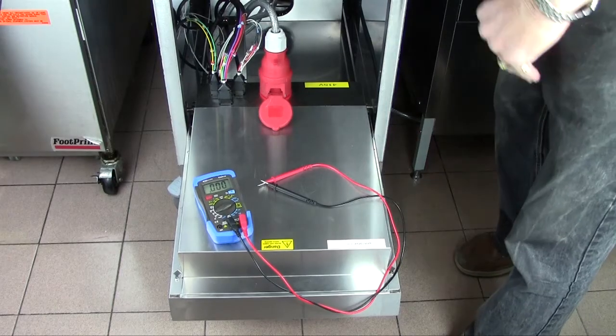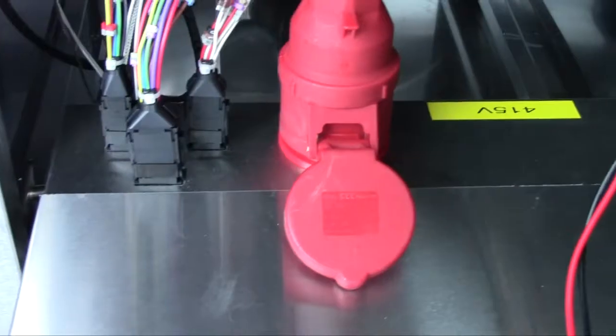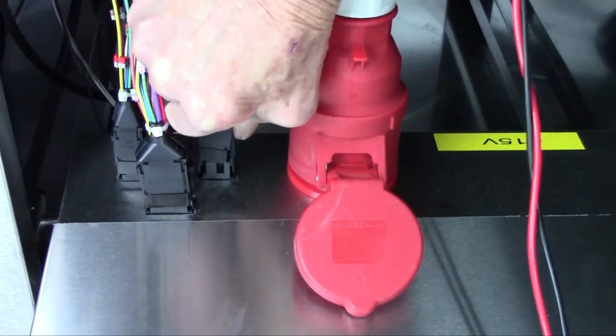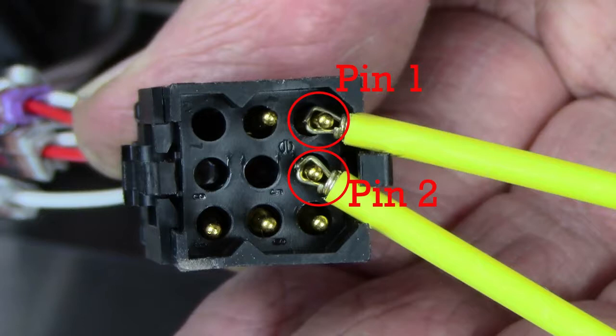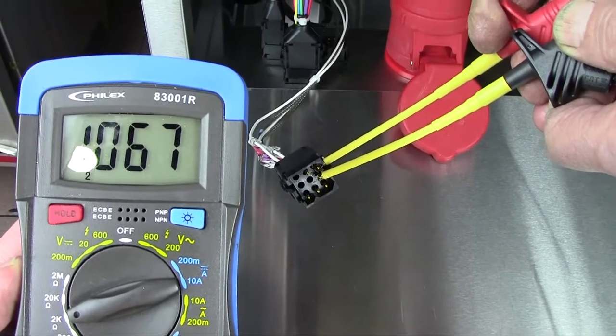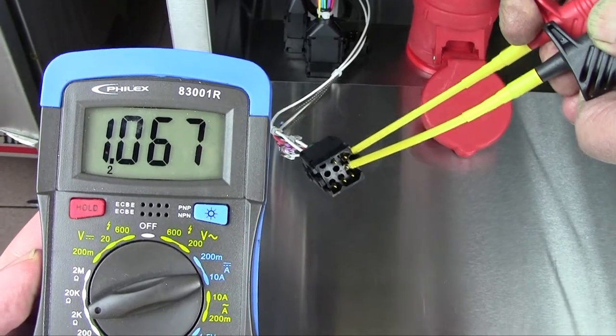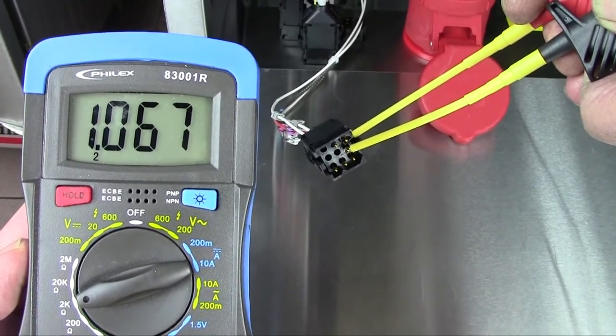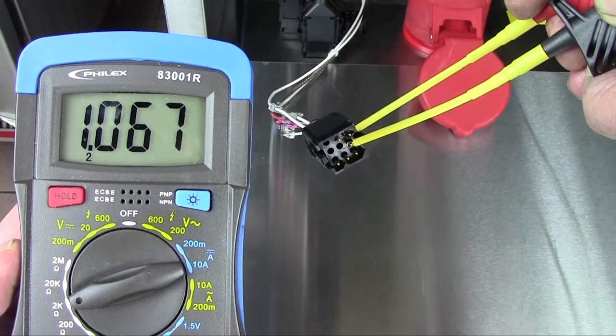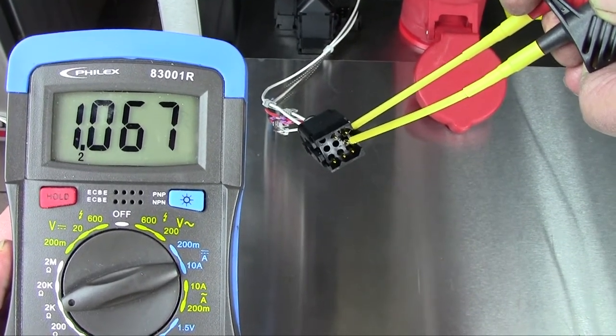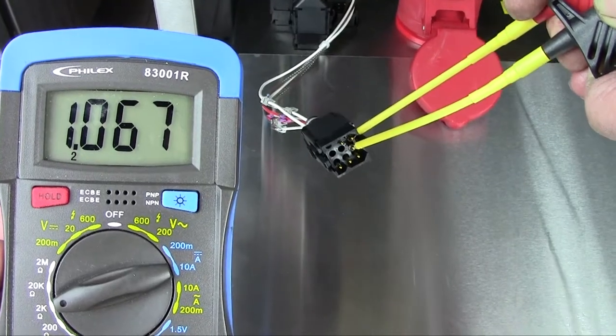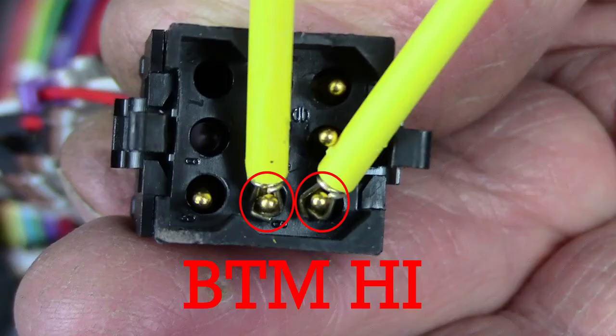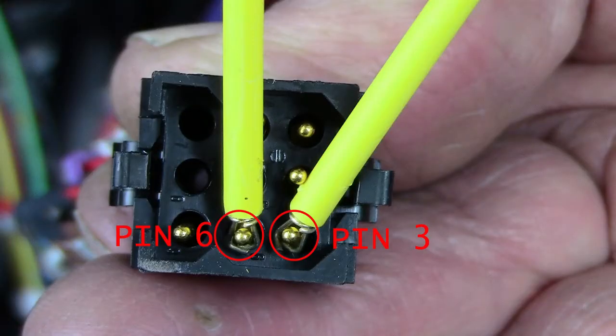If the machine is showing top or bottom high, remove the 9-pin plug and test on pins 1 and 2 for the top. It should read 1000 ohms plus or minus 60 ohms. This is due to ambient temperature, the variation. And to check the bottom, check pins 3 and 6, and that should read 1000 ohms plus or minus. If they're correct, then proceed with the rest of the checks.